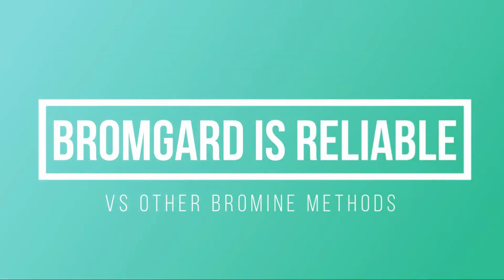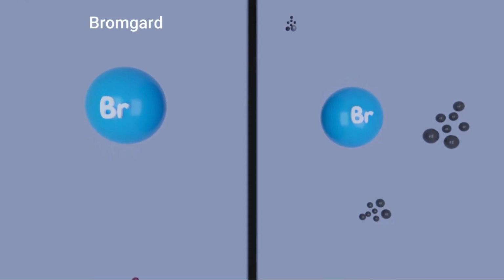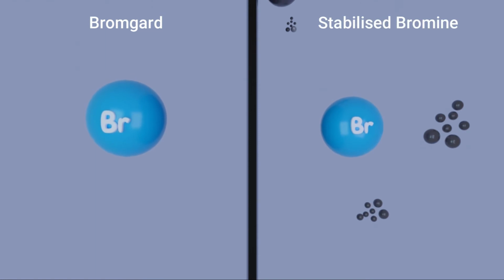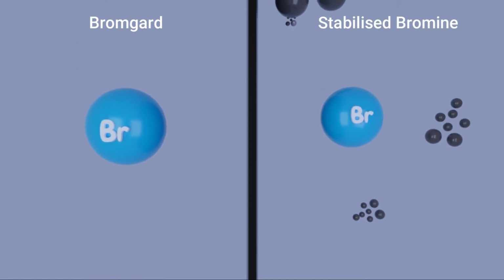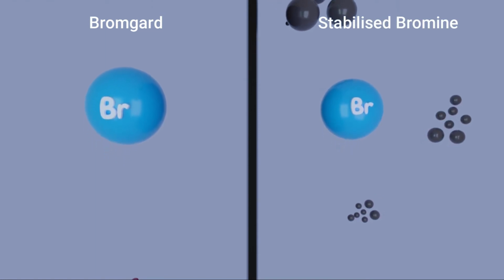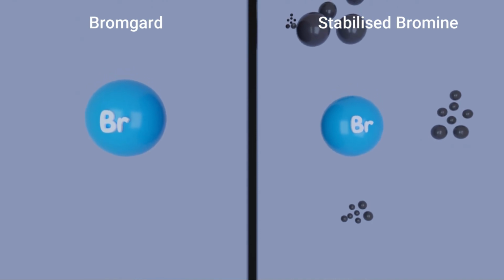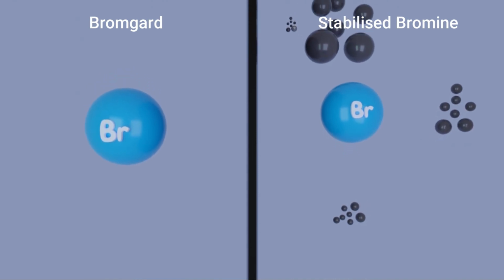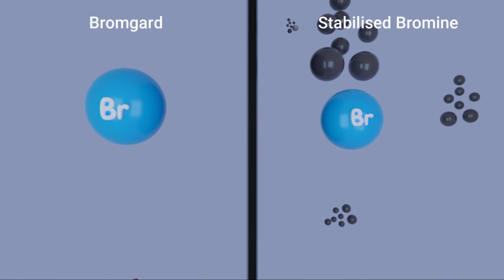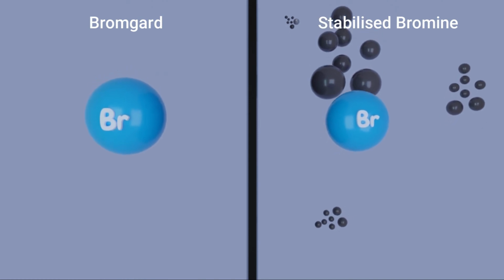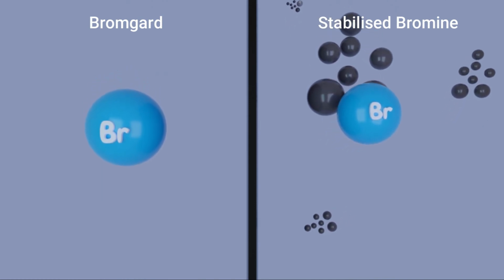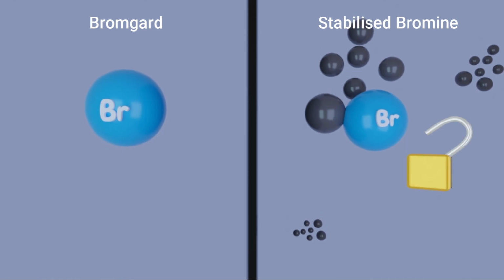So what makes Bromgard more reliable? A key difference between Bromgard and other commonly used liquid bromine systems is that Bromgard doesn't suffer from halogen lockout, a common problem with stabilized bromine products. Halogen lockout occurs where the stabilized bromine product is overdosed into the system, leading to high concentrations of the stabilizer, which will impact on the release of free bromine.